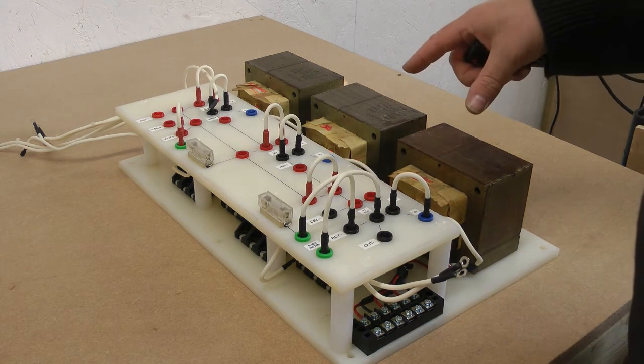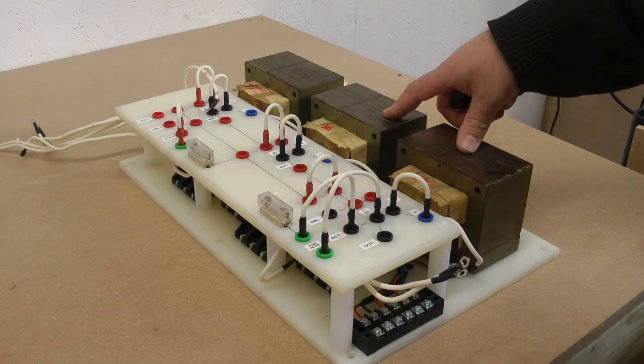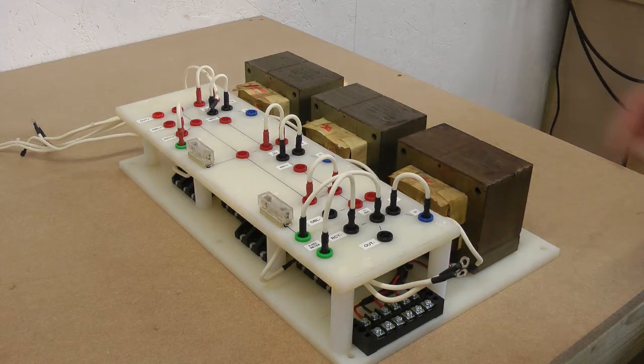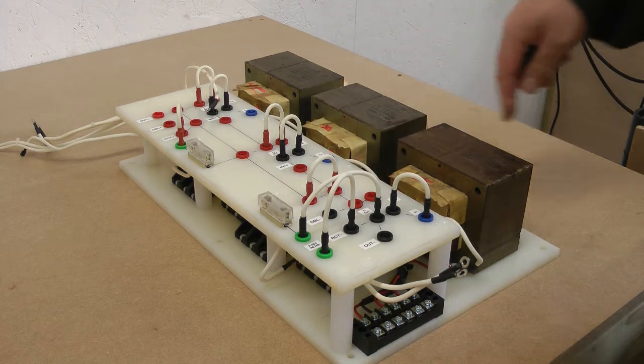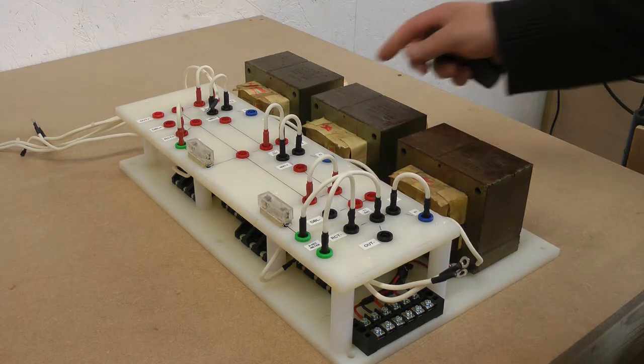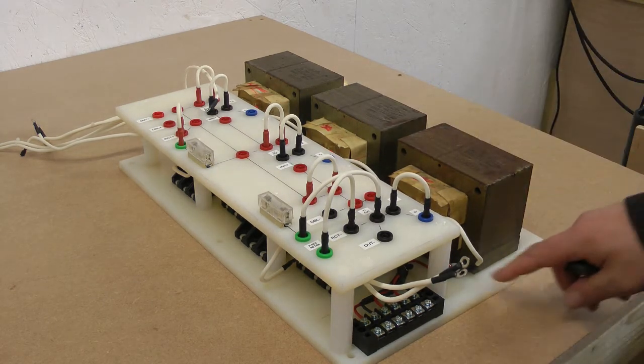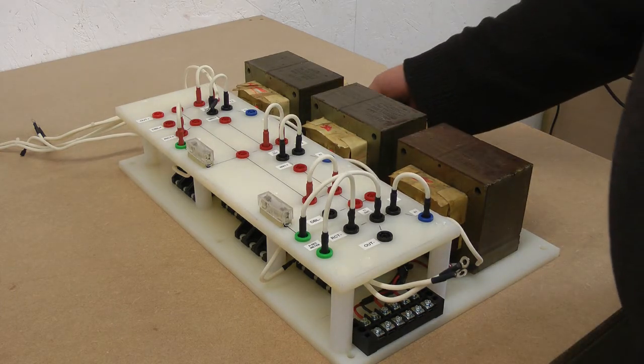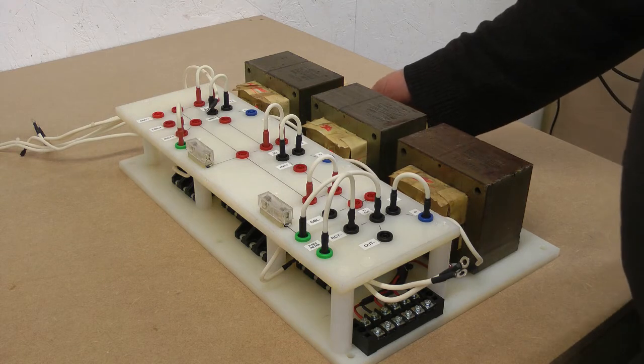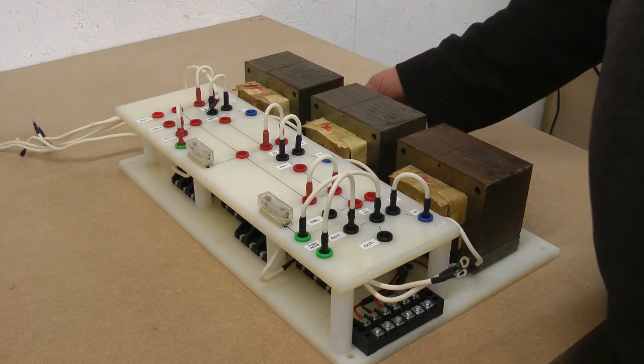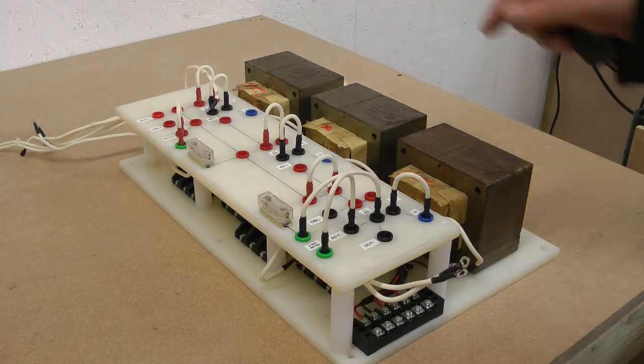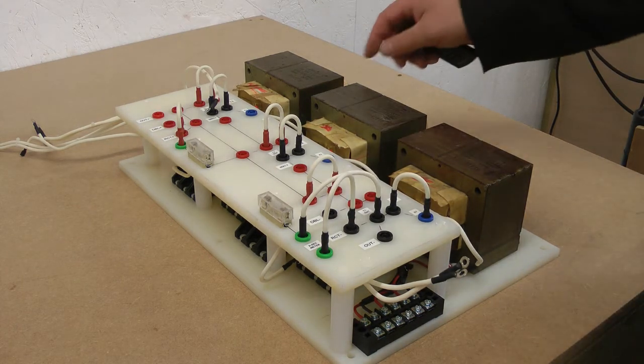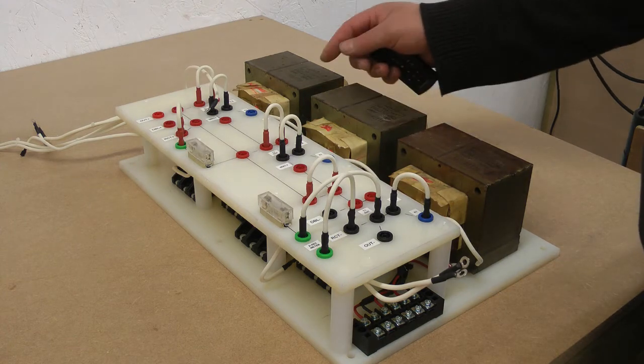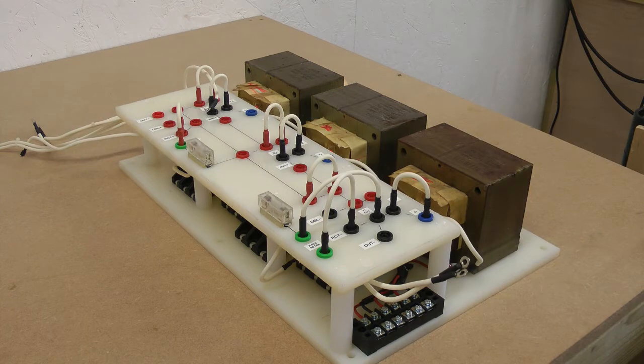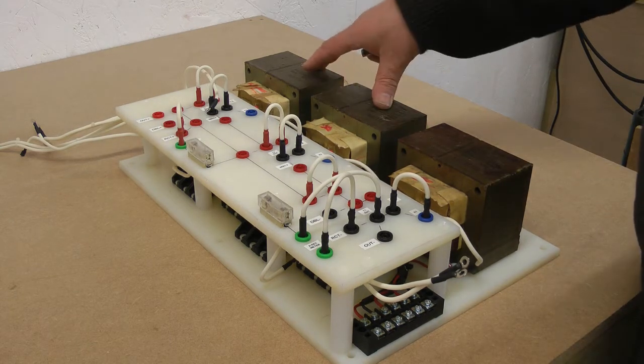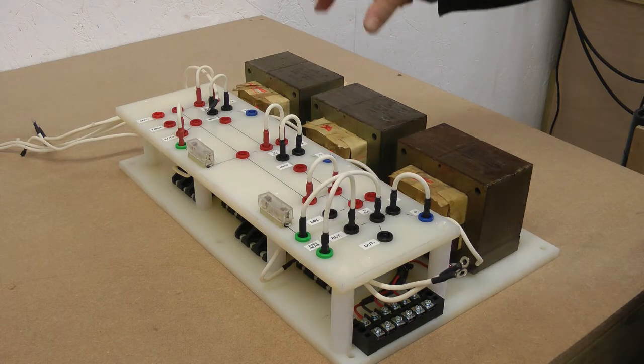We wouldn't ordinarily connect more than 2 transformers in series on top of each other, because you have to consider the core voltage to the primary. Although these are not relative to earth because they're mounted on a nylon plastic base, it does affect the potential difference between the primary, which is essentially at the line supply, and the core. What you don't want to do, if you take it too high, is run the risk of breakdown between the core and the windings of the primary. Putting 2 in series above is too much.